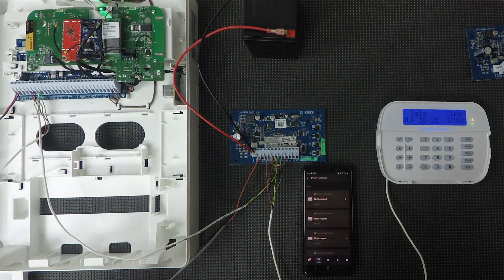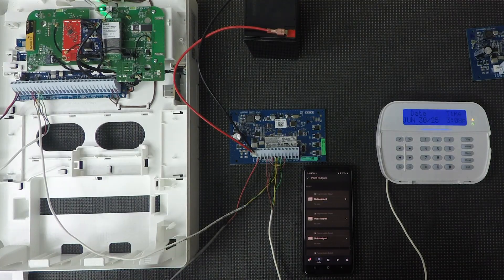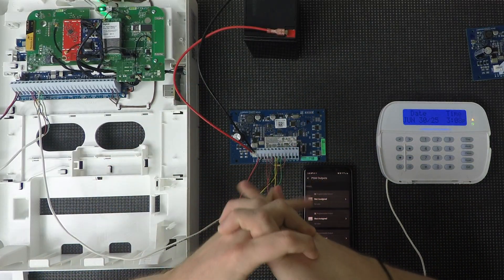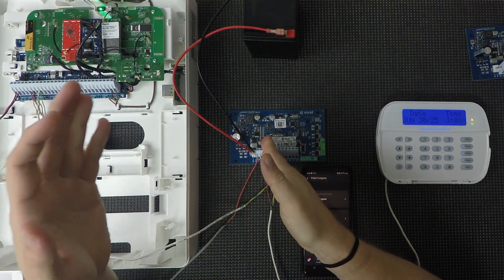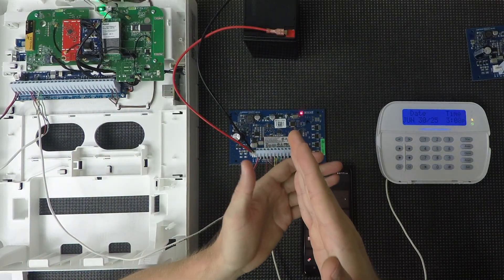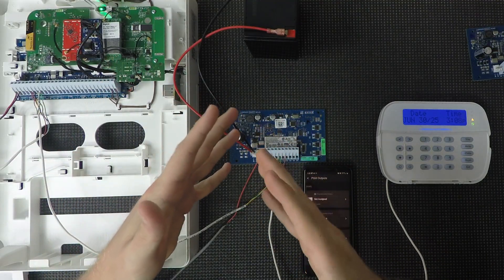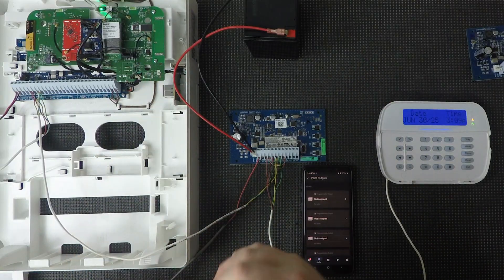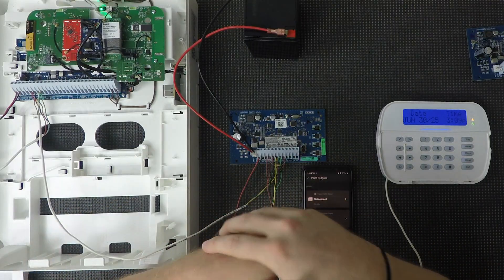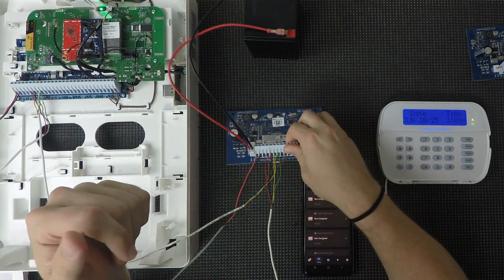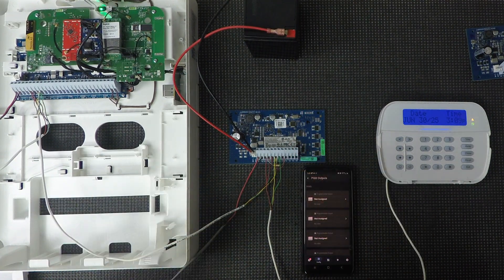So there's not a whole lot to these modules. However, there are a couple major things to remember. Like I said, remember to always use aux plus when you're pulling power from this device. A lot of times it's better to use a device like the DT 600 that we carry on our site. It's basically a wire splitter. So you take a wire from aux plus connected to the top of the DT 600 and then you get six terminals off the side that can use that one power terminal. Essentially, it is best whenever you're using one of these modules to plan out your wiring very well and make sure that you have all the necessary accessories to help you organize this in a way that is convenient for you. You can just connect everything up here and terminals are quite large. You can fit a lot of wires in there, but it does get very messy very quickly as you can see.